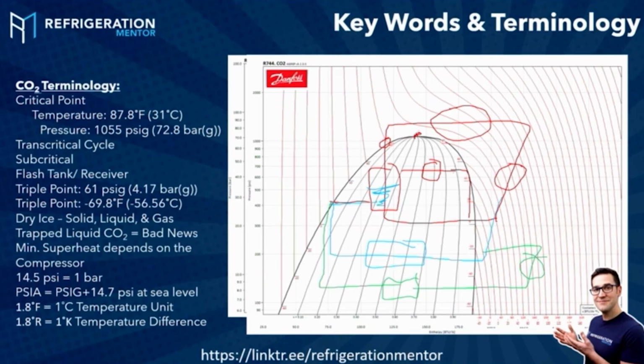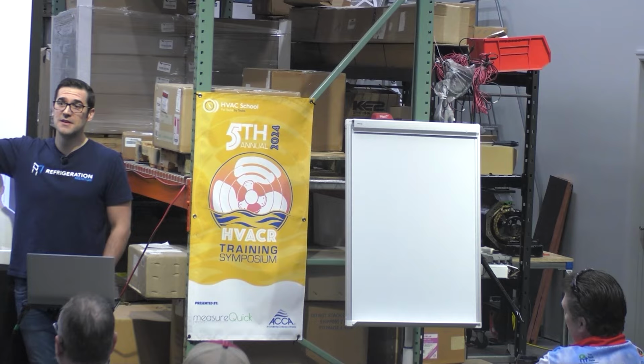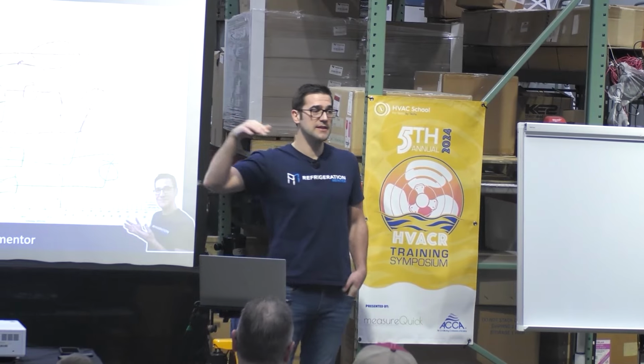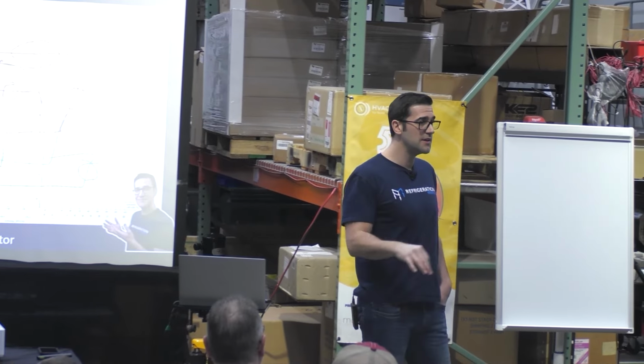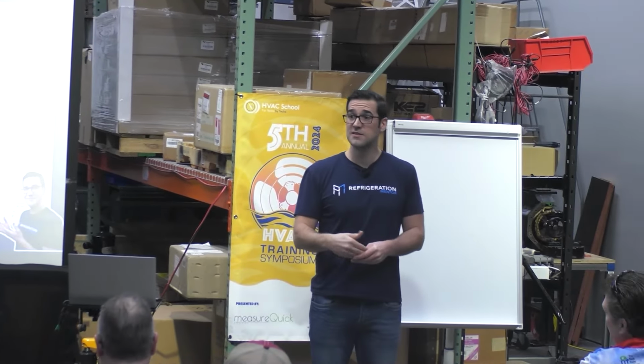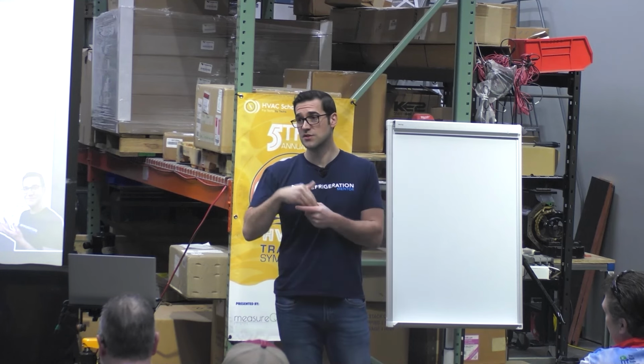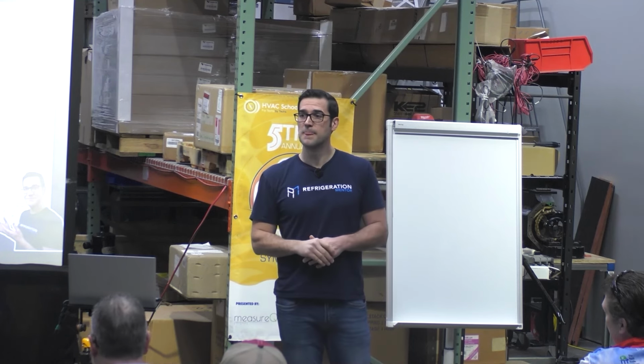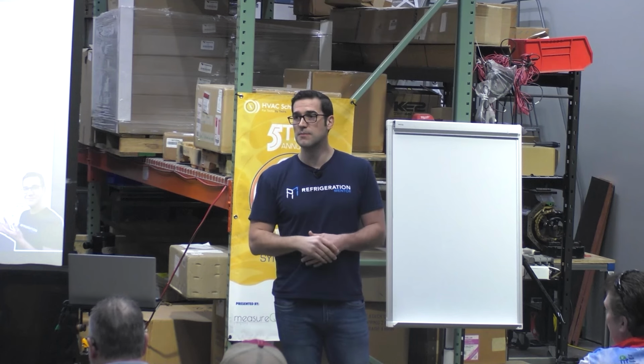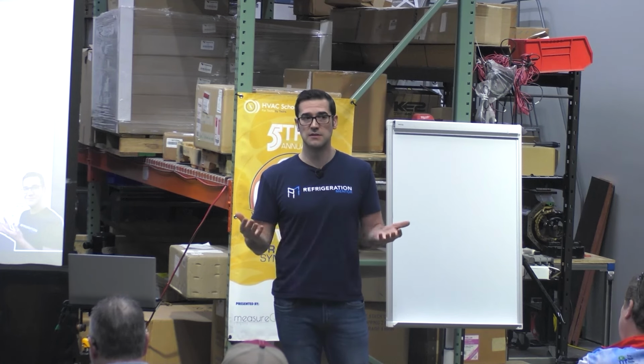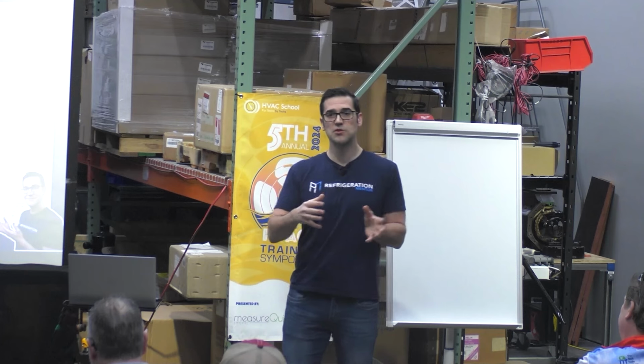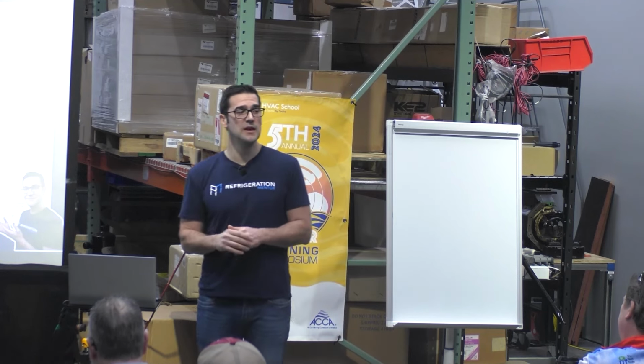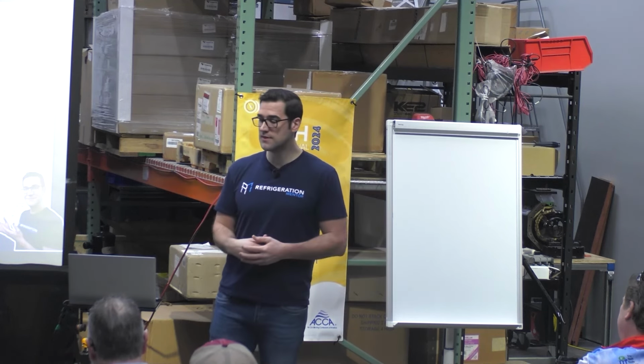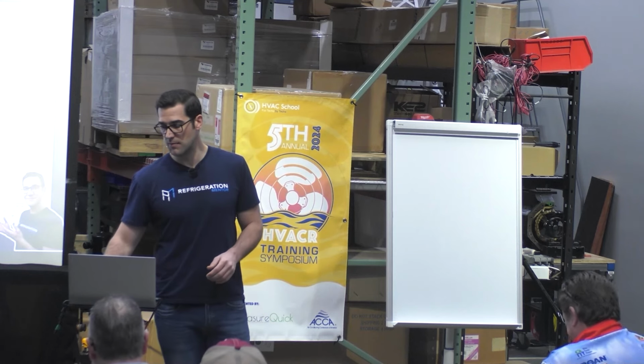So this condenser is down here, and now it's condensing. If you don't get above that 87.8 degrees Fahrenheit or 31 degrees Celsius, you just run as the systems you're working on today. Pressures are still a little bit higher. You could be running at 900 PSI on your discharge. But it's only pressures. If you troubleshoot in temperatures, you wouldn't think of it. We'll talk about a few of the safety things when you're dealing with higher pressures like that.